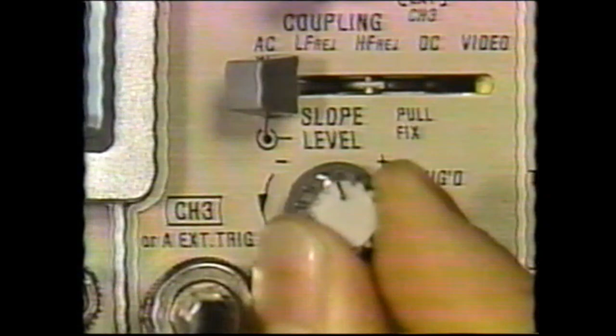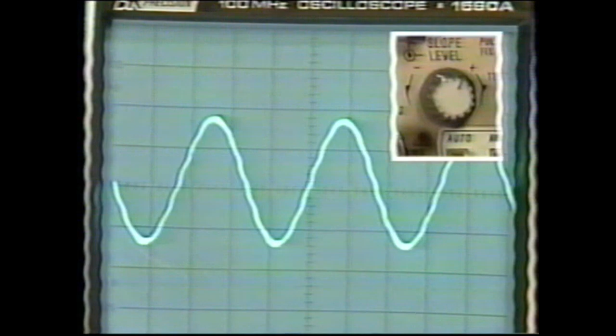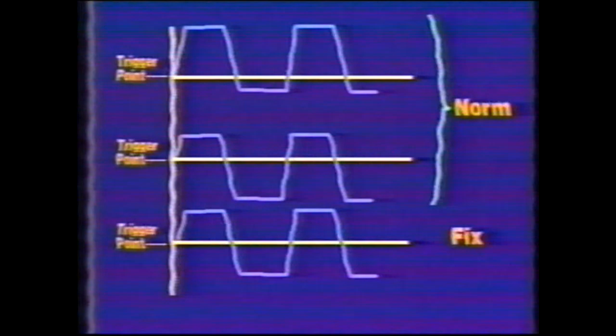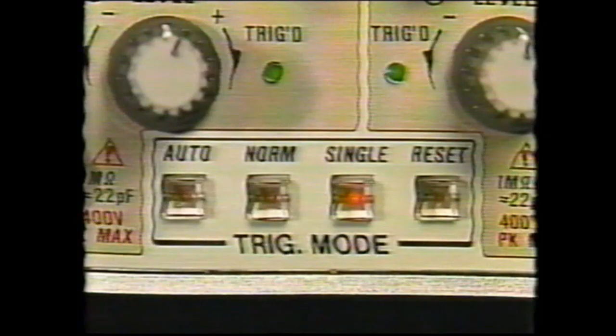The slope control allows a choice of triggering on either the positive or negative slope of the waveform. The level control adjusts the start of the sweep to almost any desired point on the waveform. At the extreme positive or negative position, there will be no sweep. With the pull-fix control, triggering always occurs at the average level of the waveform, eliminating the need to adjust the trigger level. The trigger mode has 3 operating positions: automatic, normal, and single reset.